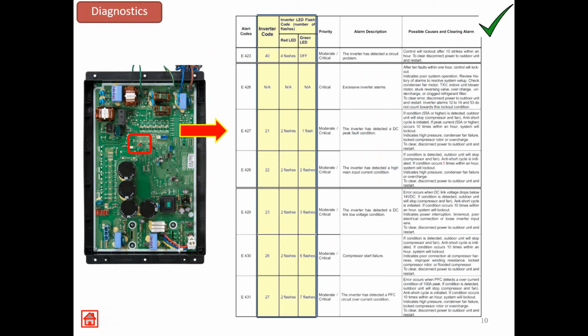The 400 codes that we're showing here right now, the 426 to the 431, these are codes that I generally see with refrigeration issues or voltage issues to the unit. If you get one of these error codes here, then one of two things is generally going on. We've got some high voltage spikes, or the compressor's not ramping up based on refrigerant charge and things like that. We've discussed earlier in the week how important line set selection is for some of this equipment. And this is really where it comes in.